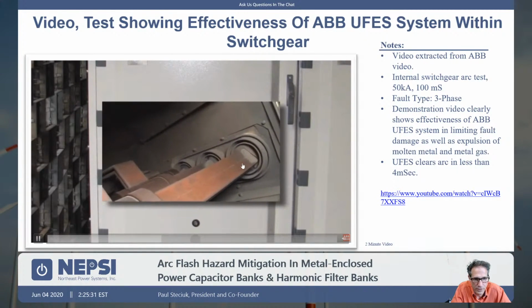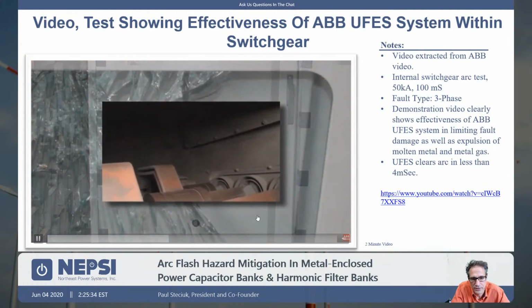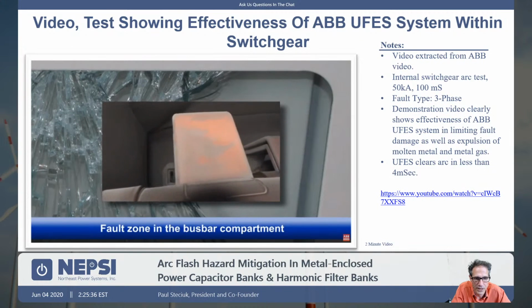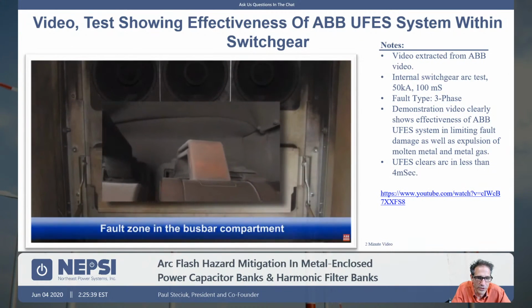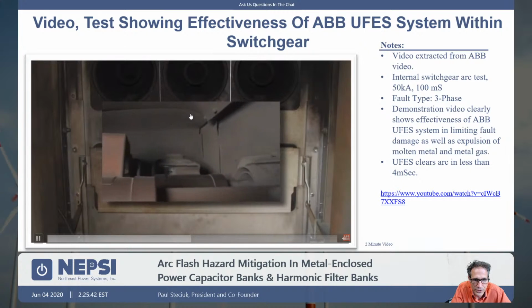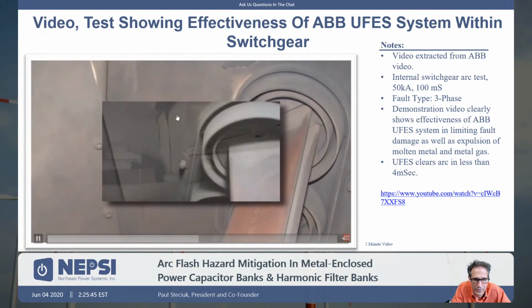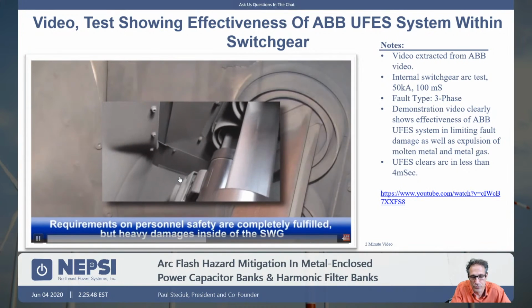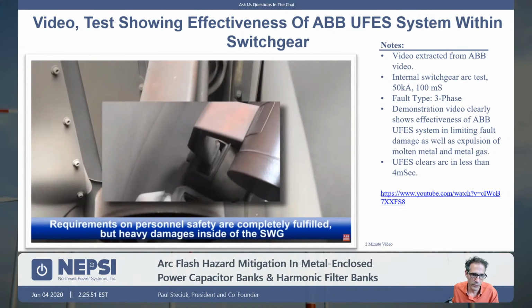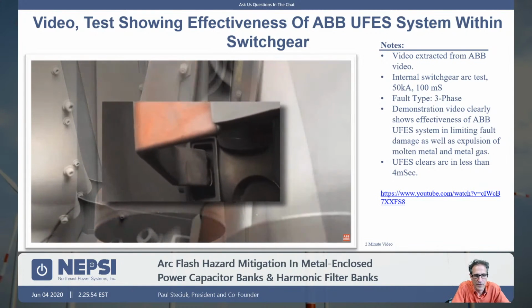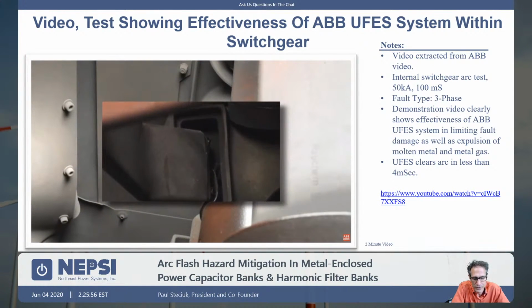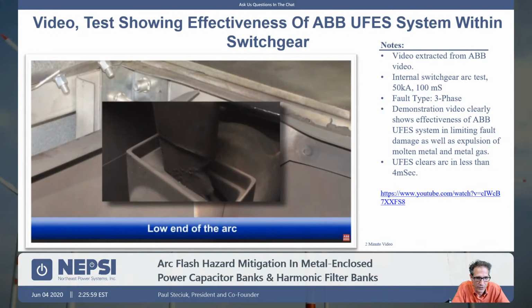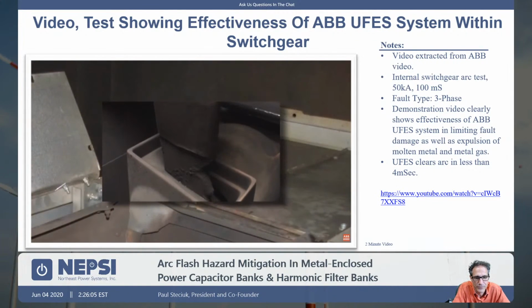So after a 50 kA 100 millisecond fault, this is the switchgear that did not contain the UFES system. You can see there's significant damage. This switchgear would need replacement. The steel is bent within the switchgear itself. You can see it received a significant amount of pressure buildup, and it would require replacement. This would be true if it were a metal enclosed cap bank or harmonic filter bank. If there was a fault of that level, it would create damage and would potentially require the replacement of the equipment. For a mine application or some other process, that would be a very costly item because the plant might be required to shut down.